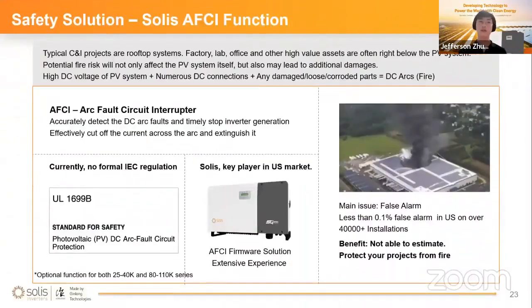Also for the safety solution, there's the AFCI function, because typically commercial projects are rooftop systems, factories, labs, offices, where high value assets are often right below the PV panels. Potential fire risk will not only affect the PV system itself, but can also lead to additional damage to the assets in the building. With higher DC voltage plus more connection points, if any accident like damage or hail happens, it can cause a DC arc, which is quite dangerous.